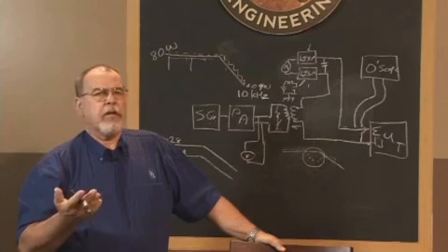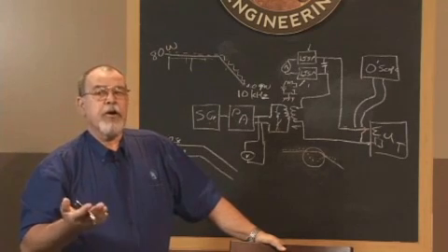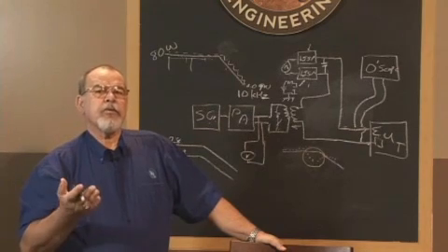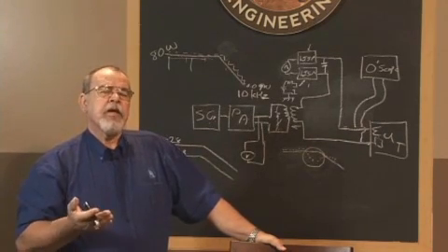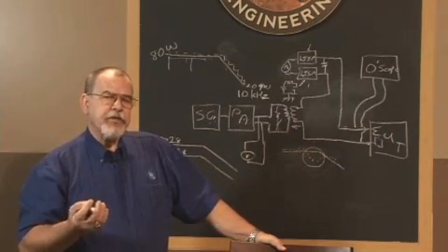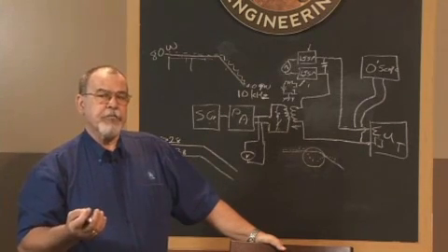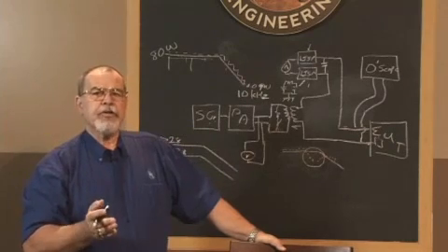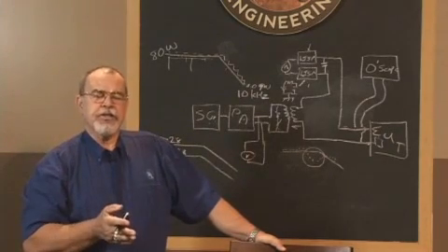How about a temperature change for a monitoring circuit? The video goes distorted. At what point do we have pass-fail? And remember, these pass-fail criteria need to be objective, something like a 10% variance in the measurement, some hard number that you can say this is acceptable and this isn't.